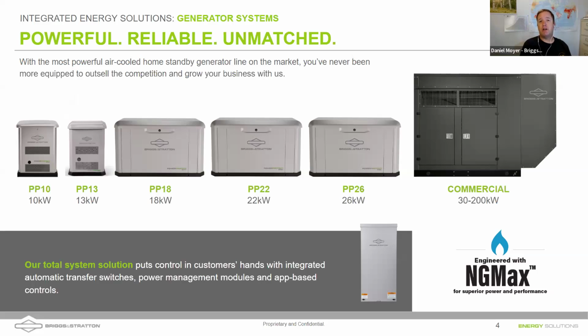On all of these generators, if you run a generator on propane, say it's a 22K generator, you're going to get 22K of power out of it. But these generators derate when you run them on natural gas—not ours though. We've adjusted some of the ignition timing so that we can now produce 22 kilowatts whether you're running it on propane or natural gas. We're really excited to offer these, and we're going to talk about how you can combine the two together as well.